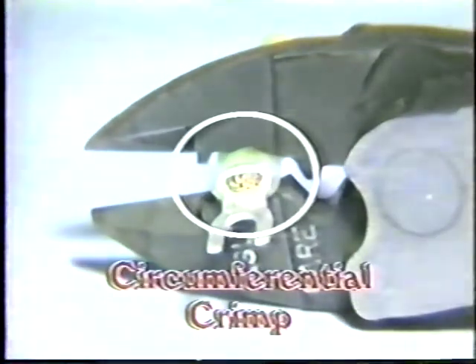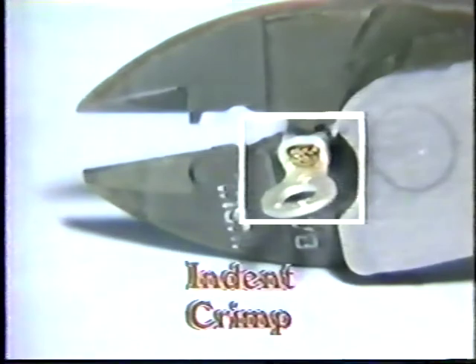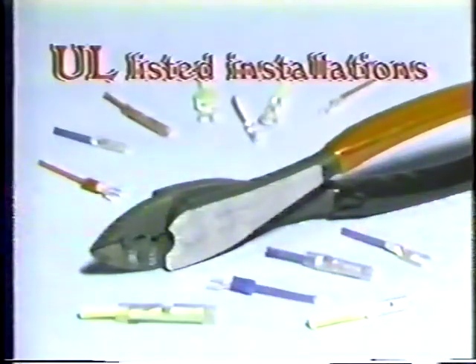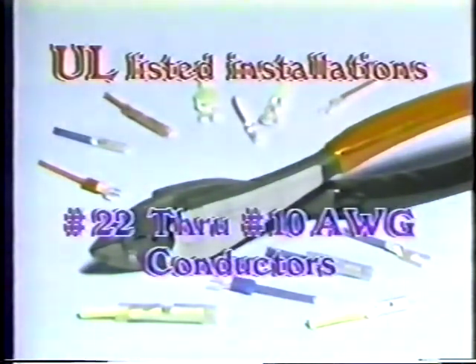Because space may not permit an electrician to carry two crimping tools, Burndy developed the Y10D Hytool, the one installation tool which provides a circumferential crimp for insulated connectors and an indent crimp for bare terminals and splices. The Y10D provides UL-listed installations for the complete range of number 22 through number 10 gauge conductors. Because competitive designs require one tool for insulated and a second tool for uninsulated installations, Burndy's Y10D is definitely the one tool to carry.